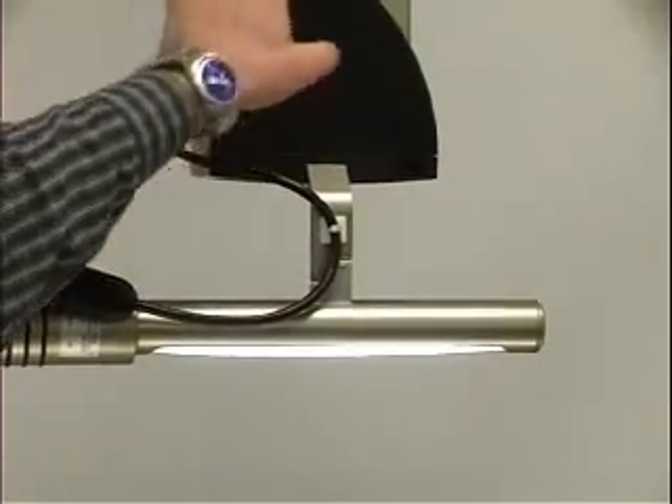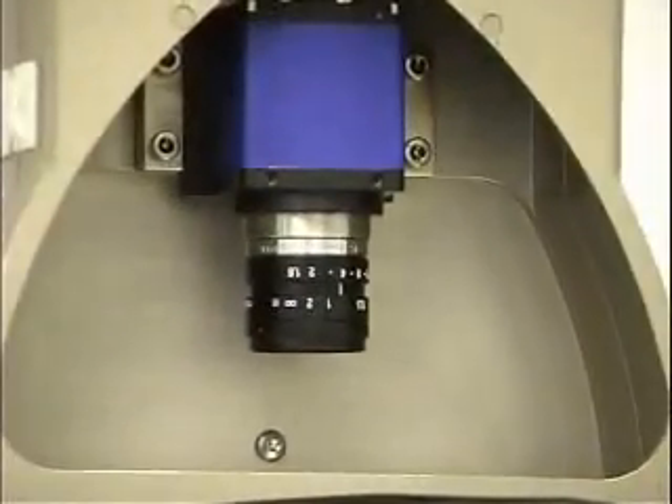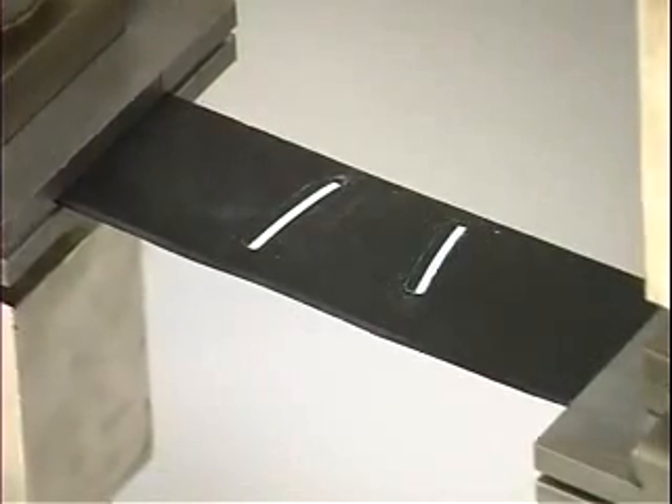The video extensometer is also used to control the specimen stretch. The area of interest is defined by the gauge marks that are present both in the longitudinal and transverse direction of the specimen.